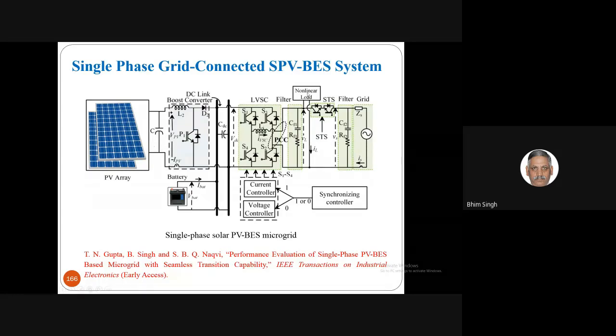But here, since we have energy storage, we will not lose the generation. We'll feed the load, and the excess power will go into the battery, and when the grid is not there, we can still feed the load. There's also a mode where, when the grid is there, you can feed constant power to the grid, so the grid should not see whether your solar generation or load is changing. The intermittency of the load and solar generation is not reflected on the grid, and the grid's intermittency is not reflected in the load, so the load gets uninterrupted power similar to a UPS.